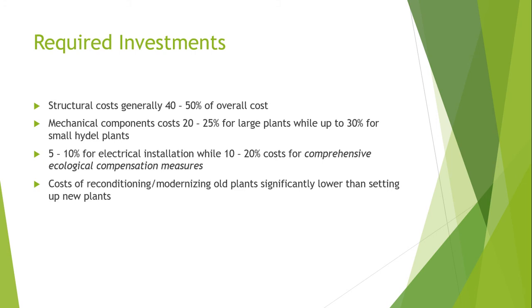The costs are very location dependent, and generally valid guidelines cannot be established. In many cases, the cost for structural components is estimated to be around 40 to 50 percent of the overall cost. The mechanical components like turbines, transmission, and regulatory systems are approximately 20 to 25 percent for larger plants and up to 30 percent for smaller systems.